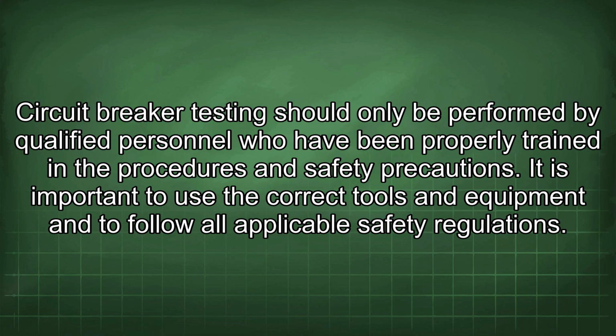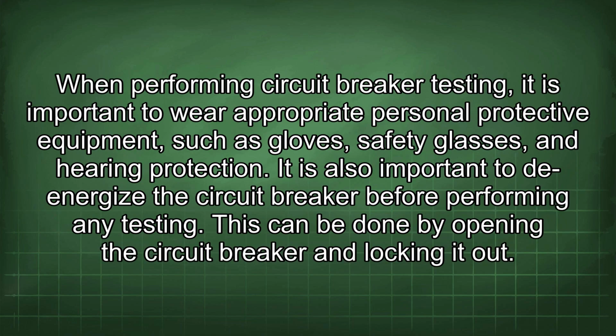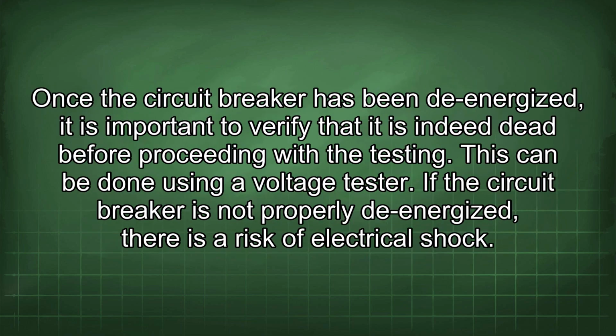Circuit breaker testing should only be performed by qualified personnel who have been properly trained in the procedures and safety precautions. It is important to use the correct tools and equipment and to follow all applicable safety regulations. When performing circuit breaker testing, it is important to wear appropriate personal protective equipment such as gloves, safety glasses, and hearing protection. It is also important to de-energize the circuit breaker before performing any testing. This can be done by opening the circuit breaker and locking it out. Once the circuit breaker has been de-energized, it is important to verify that it is indeed dead before proceeding with the testing. This can be done using a voltage tester. If the circuit breaker is not properly de-energized, there is a risk of electrical shock.